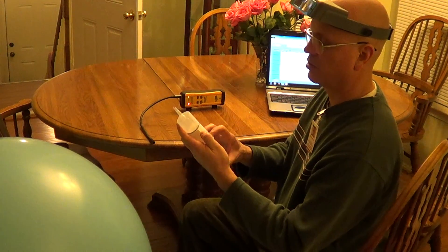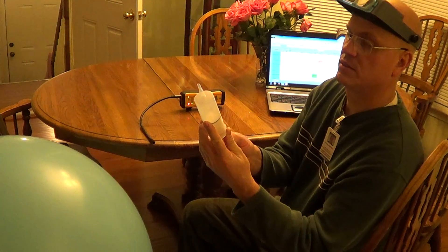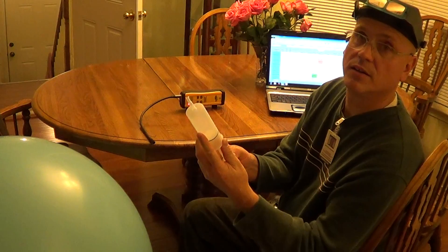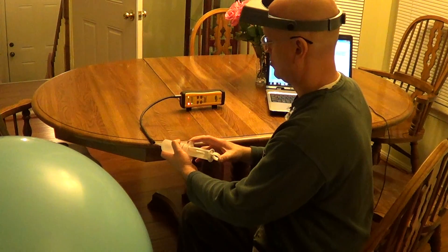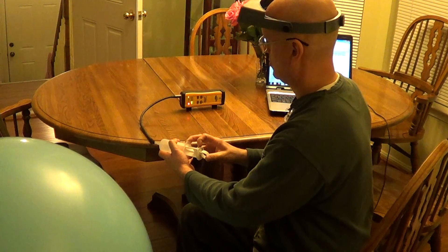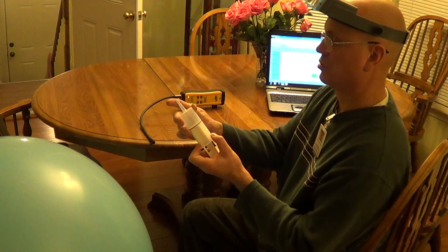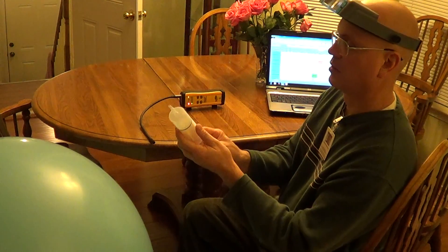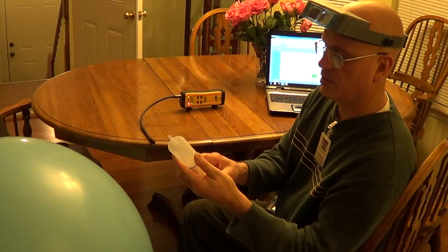Let's go to 500 parts per billion — I'm going to mix half of it with air, so 500 parts per billion. And now let's go straight to 250 parts per billion.